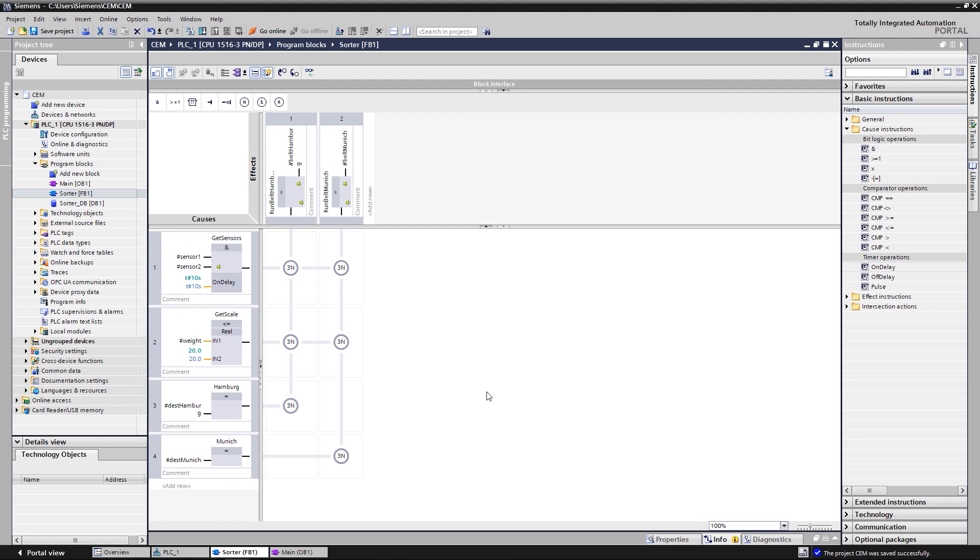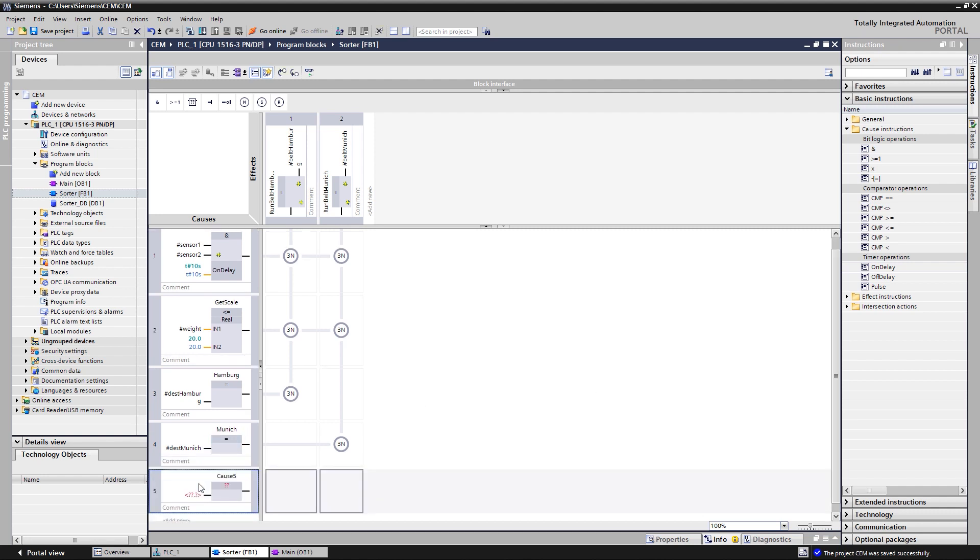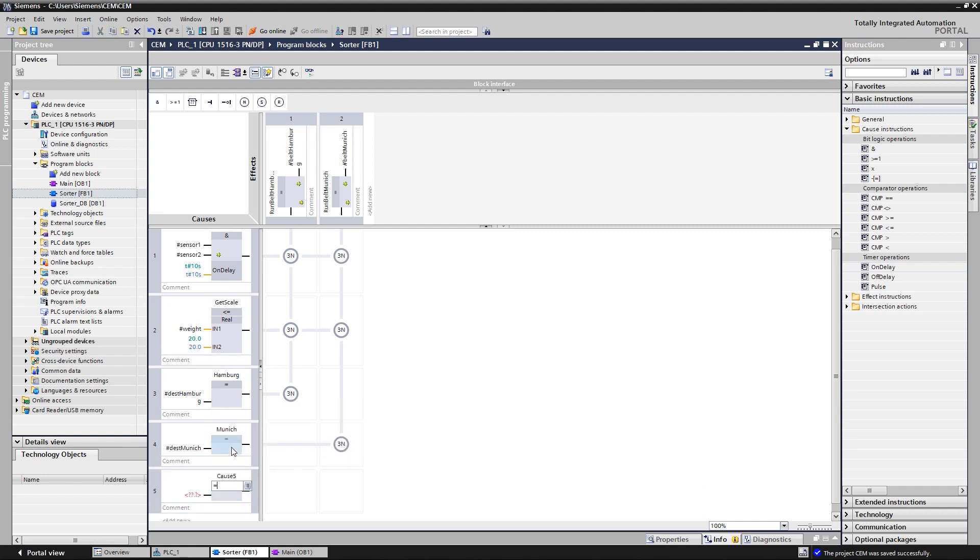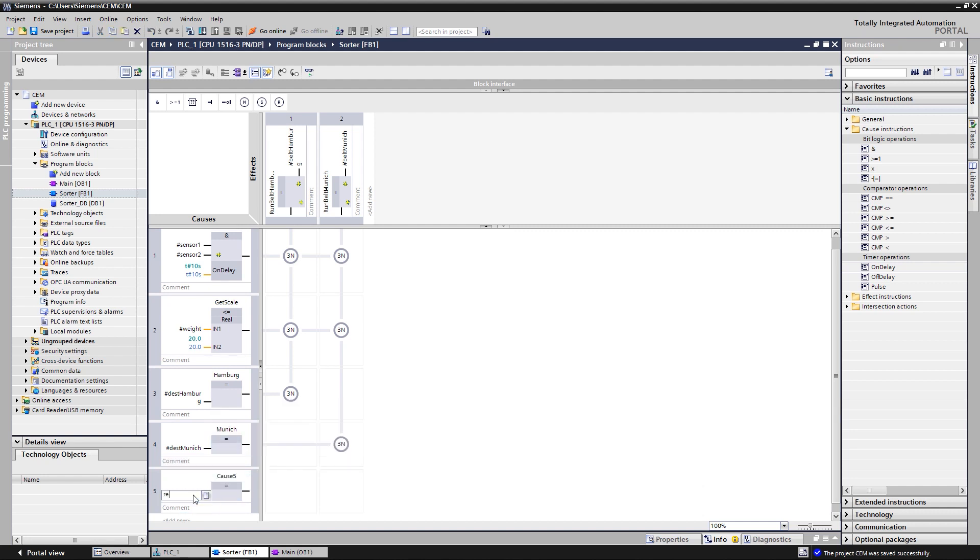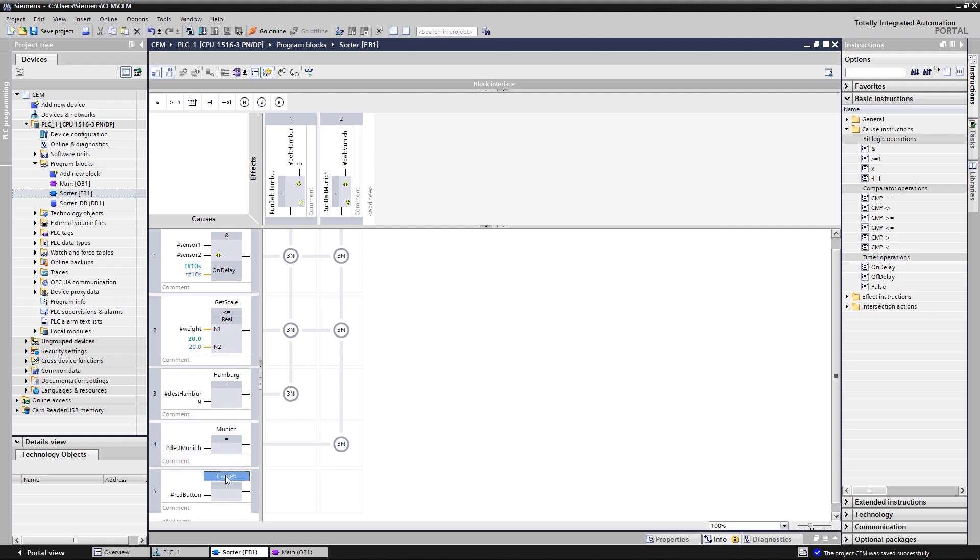The basic example should now be extended with an interlock function. Let's assume the following case. If a customs officer wants to inspect a bag, he can press a red button. When that happens, the belts must come to a standstill and a red indicator lamp must start to glow. When the inspection is over, the customs officer presses a green button to turn off the indicator lamp and to restart the belts. So, cause 5, which is called luggage check, is added to the matrix and linked with the signal of the red button.